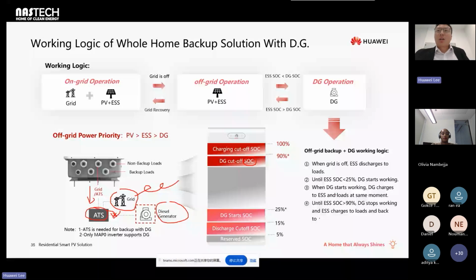And the DG charges the ES and supplies the load at the same moment, until the ES SOC is bigger than 90%. Then the DG stops working. At this time the DG provides power to the ES and the loads, and when the ES is enough to cover the loads, it sends the signal to the ATS and turns off the DG, and continues to use the PV and the ES to charge and discharge. And you can modify this setting by yourself.